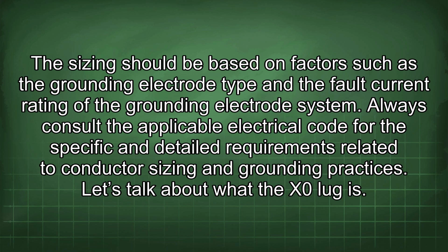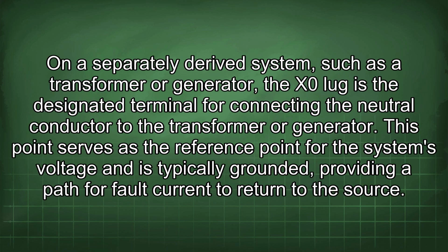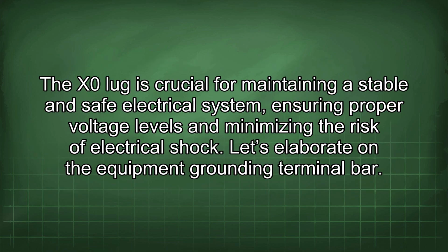Let's talk about what the X0 lug is. On a separately derived system, such as a transformer or generator, the X0 lug is the designated terminal for connecting the neutral conductor to the transformer or generator. This point serves as the reference point for the system's voltage and is typically grounded, providing a path for fault current to return to the source. The X0 lug is crucial for maintaining a stable and safe electrical system, ensuring proper voltage levels and minimizing the risk of electrical shock.